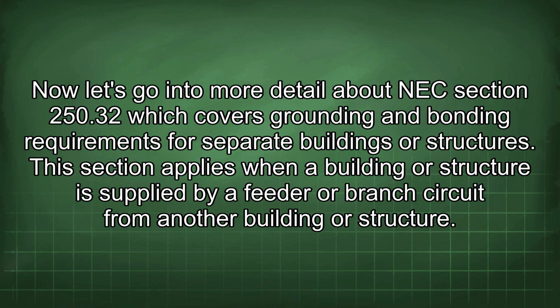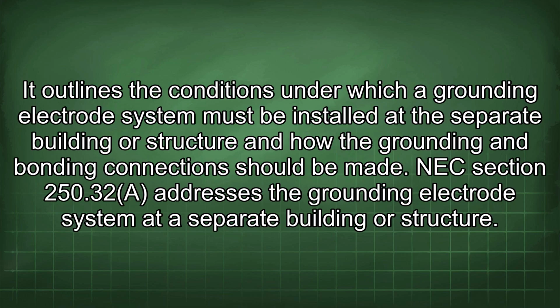Now let's go into more detail about NEC Section 250.32, which covers grounding and bonding requirements for separate buildings or structures. This section applies when a building or structure is supplied by a feeder or branch circuit from another building or structure. It outlines the conditions under which a grounding electrode system must be installed at the separate building or structure and how the grounding and bonding connection should be made.